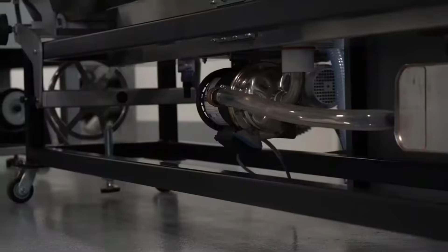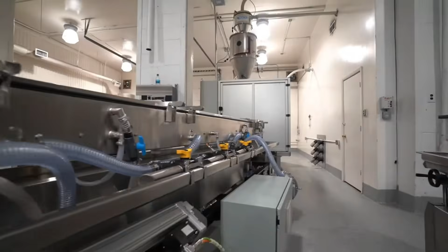from stagnating. It also helps in the cleaning ability, and you'll notice dramatically the fewer number of hoses in a vacuum tank compared to most normal vacuum tanks. Other things that have changed on this tank is you'll notice we have used what's called a triclover fitting here, but in this particular tank, being that it's not a full medical tank, there are still threaded fittings here, and threads are known to be a difficult area for cleaning. Inside the tank, there are still threads that are being used, even the thread for the drain. There are threads that are exposed, very difficult for cleaning and flushing, and known areas for bacteria to grow. And rounded corners, these are typical rounded corners, not as rounded as we like to see. And at the bulkhead, you'll notice there are still welds. Welds are very difficult to clean, and again, a terrible place for bacteria to grow and reside.